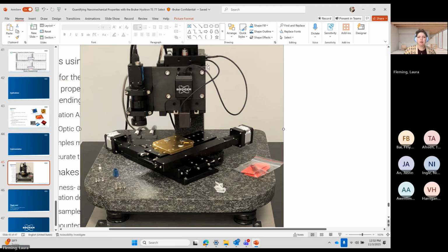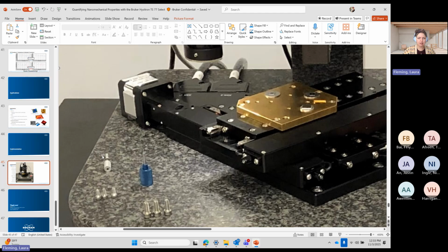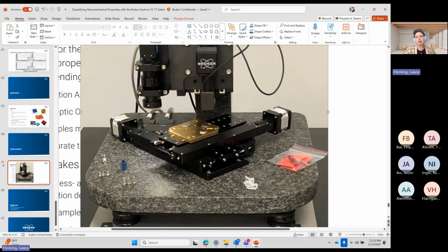Transducer is here. I don't expect that you'll be removing the piezo scanner very often, if at all. But you should know there is, on the dovetail on the side of it, a 1/16 hex screw that you screw in to get it tightened down well. The transducer has a probe that you install using this probe tool that you can see laying down on the stage here. What I want to talk about here is how to install that.